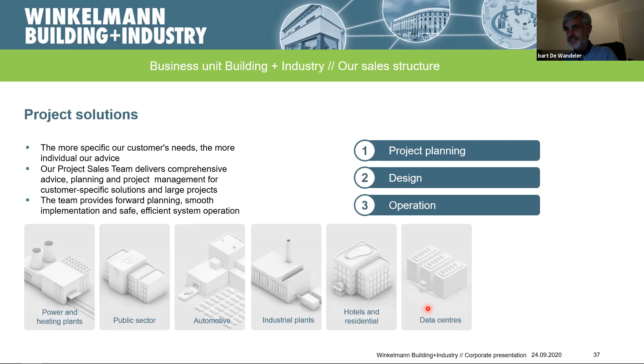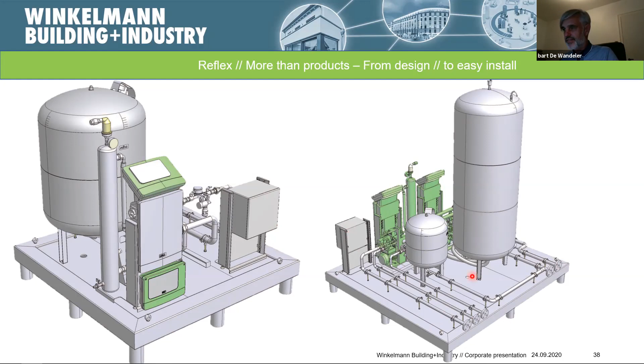We can also deliver on skids - small units where we put everything together, design everything, and make drawings for planners, who can implement them in their designs for installers to use. It's easy to install - you only need to connect the water makeup line, the connection line for the pressurization unit, and the degassing line. We have a consumer box, so you only need to connect the power cable, 200 or 400 voltage, and it's done. That's how we deliver on-site solutions to make your life easier.